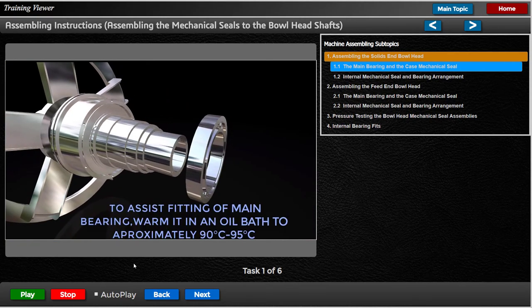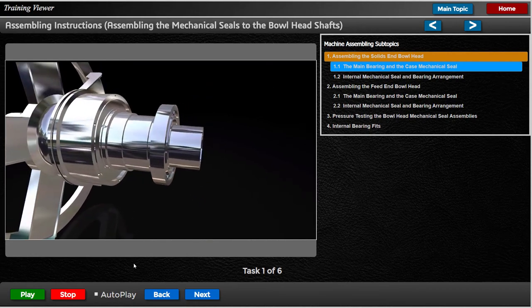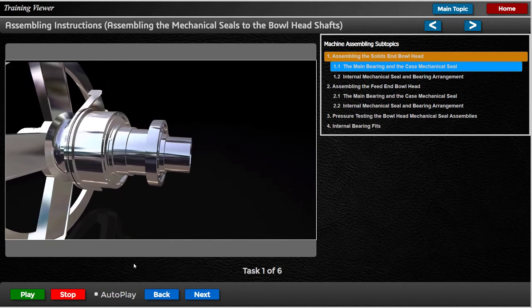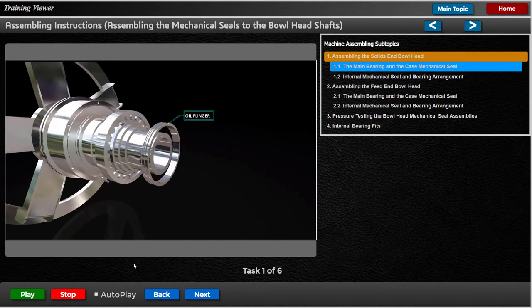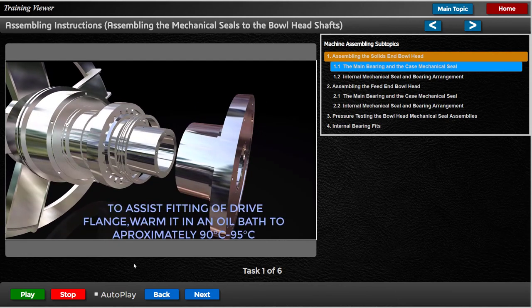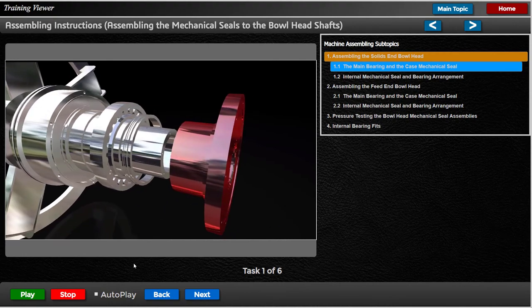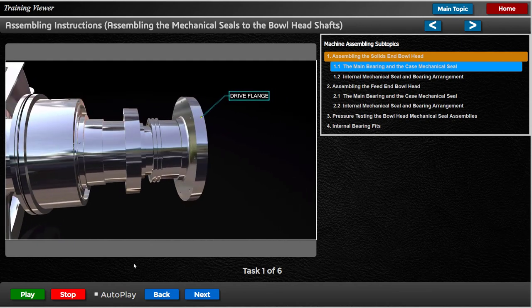To assist fitting of the main bearing, warm it in an oil bath to approximately 90°C to 95°C, then assemble the cylindrical roller bearing onto the bowl head shaft. Insert the oil flinger onto the bowl head shaft. To assist fitting of the drive flange, warm it in an oil bath to approximately 90°C to 95°C, then insert the drive flange and fix it with M12 cap screws.